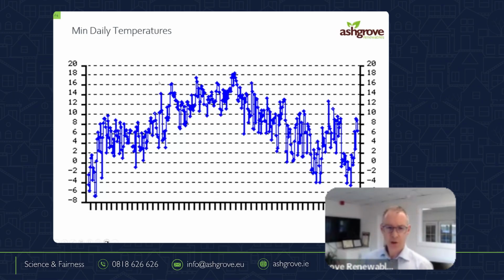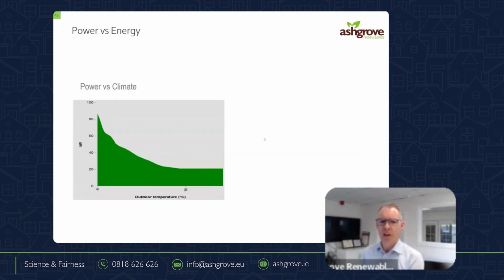So when we look at 30 years of weather data, this is what our software does, by the way. Some of the engineers online here will know, we're looking at degree day data, which tells us, yes, we do get -7, but it's not like the North Pole here all the time. We do get days that are really cold, but it's not a fair indicator. We know in North Cork its average winter temperature is 9.6 degrees or whatever it is, and that's a better indication. So when we use our software, we've just taken screenshots here out of the software.